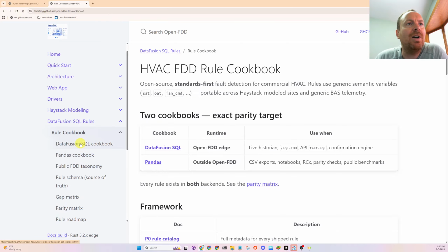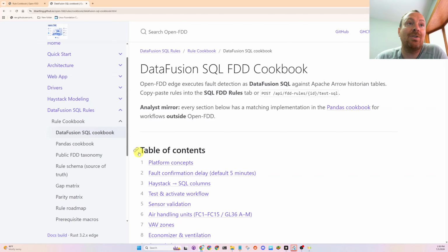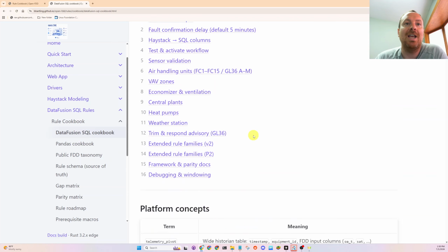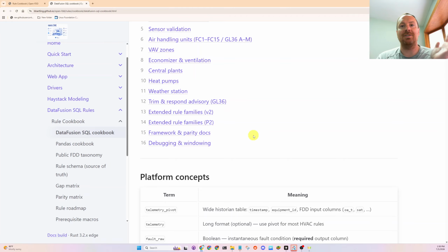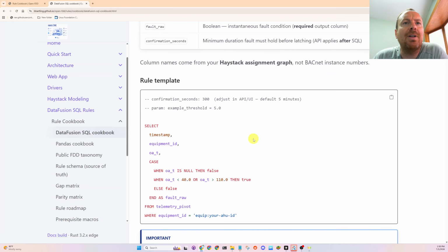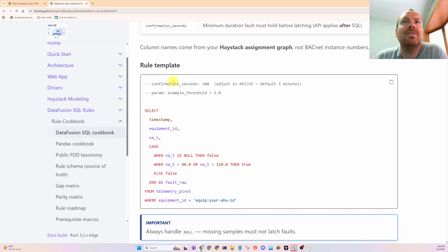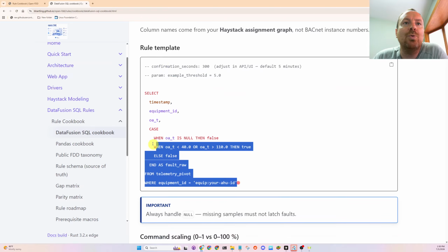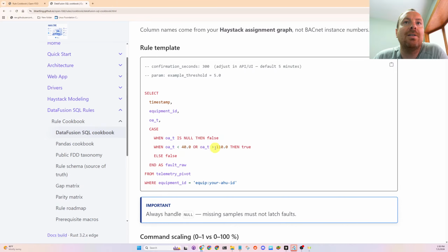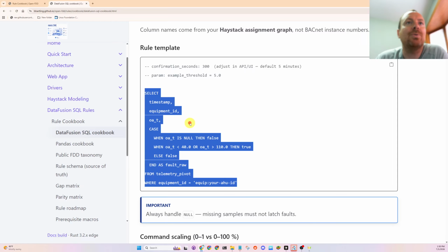So there's an SQL cookbook and a Pandas cookbook, and they should both be mirrors of each other. For example, this one is just like how a rule would be written in SQL—something like a rule for when the outside air temperature is greater than 40 and less than 110 degrees Fahrenheit as an assumption. This is what an SQL rule would look like.